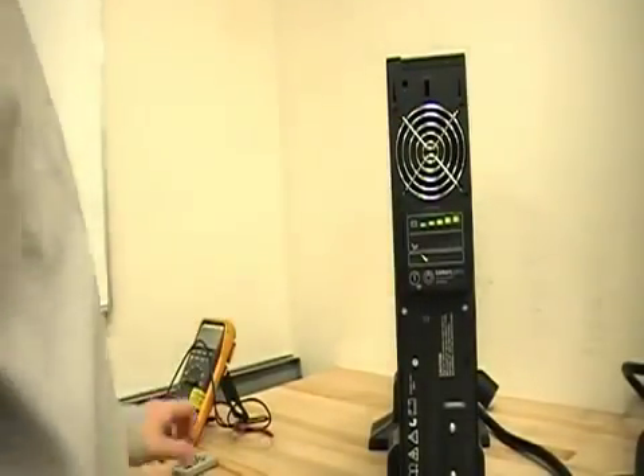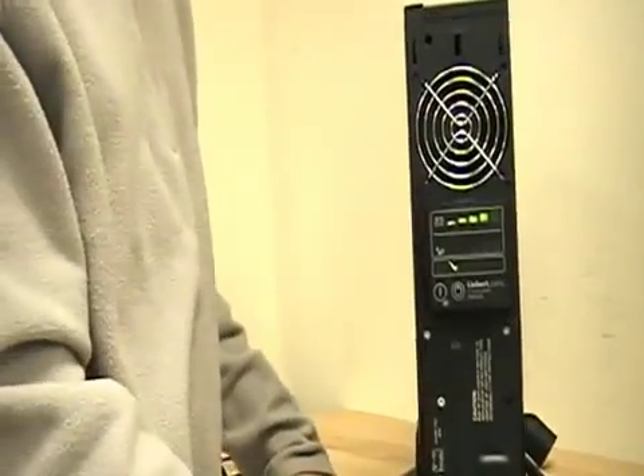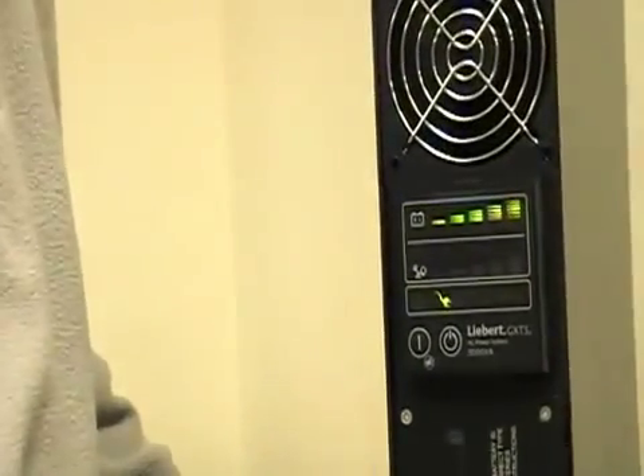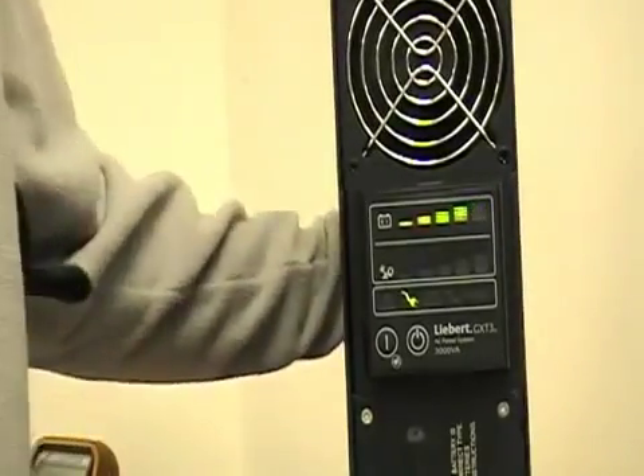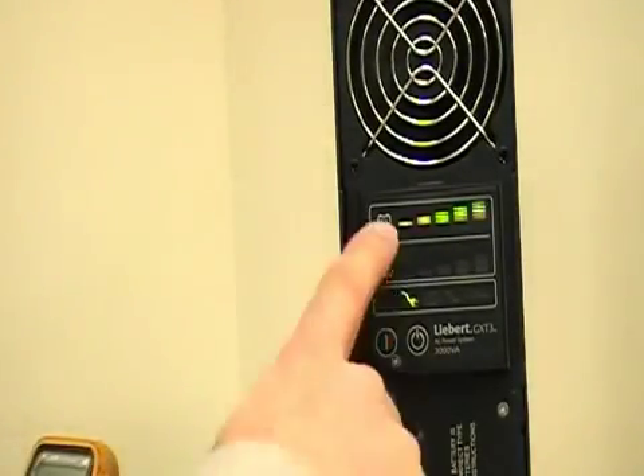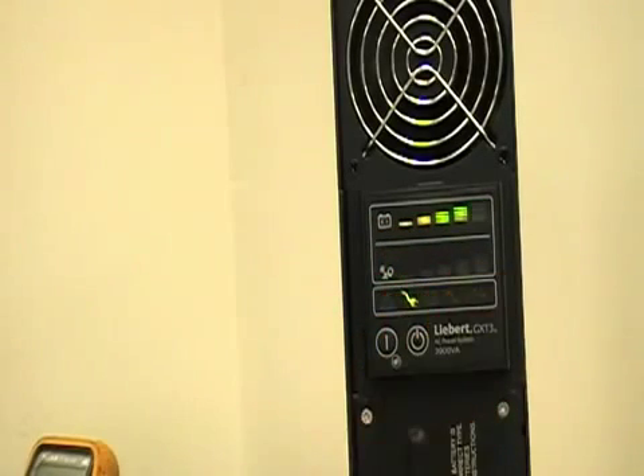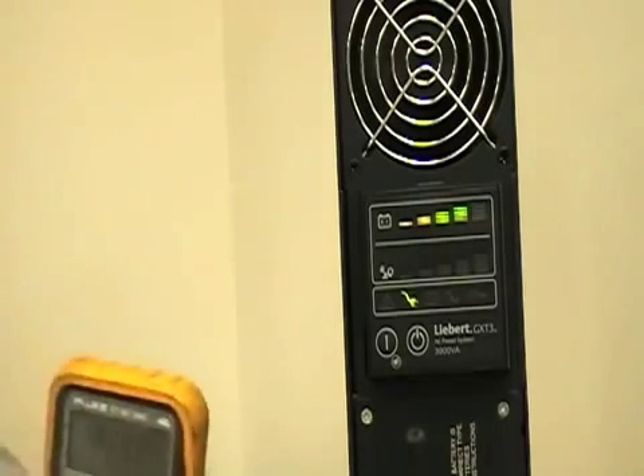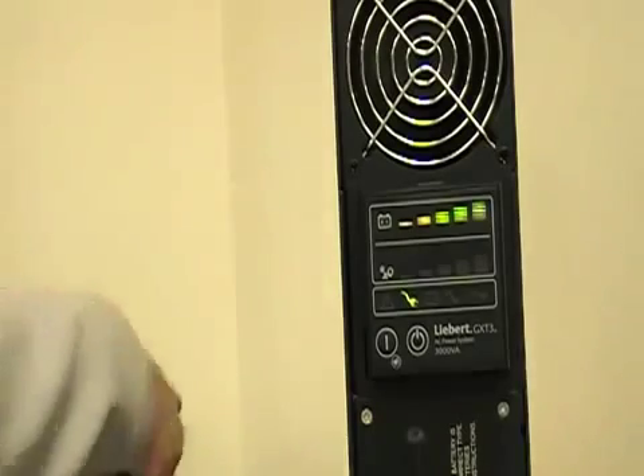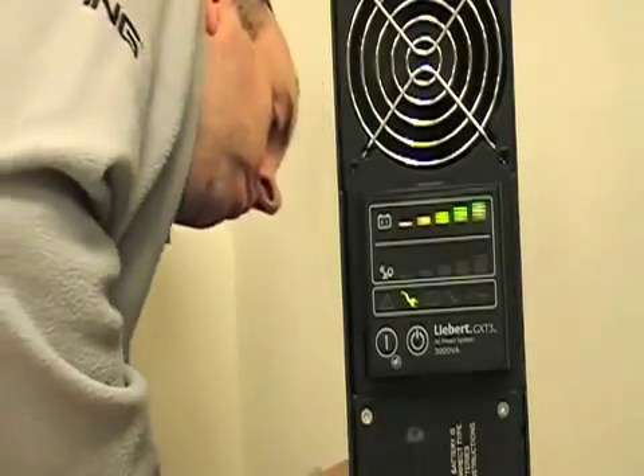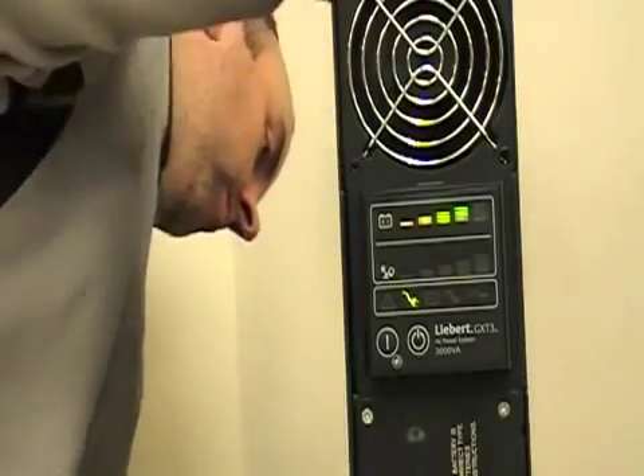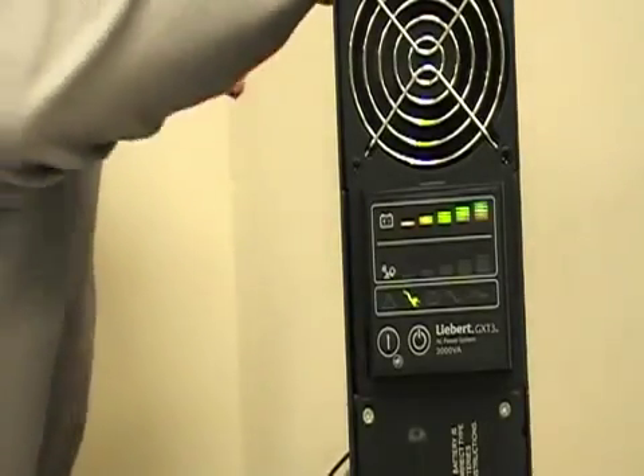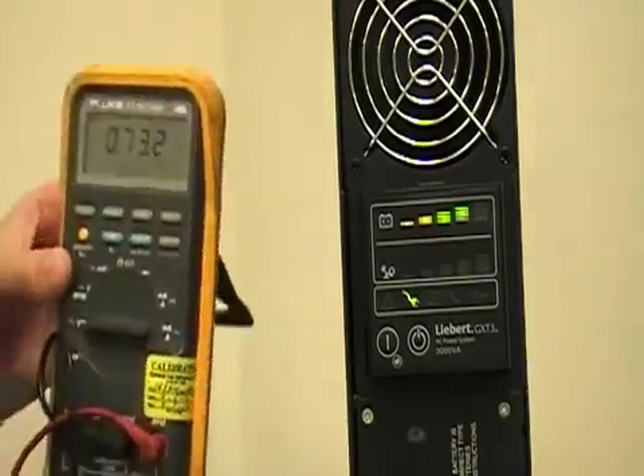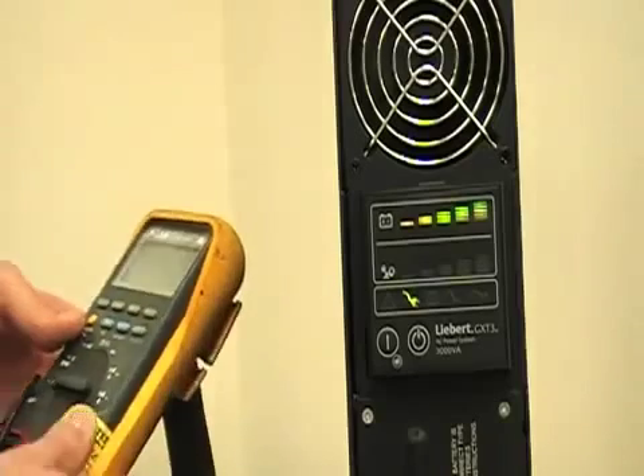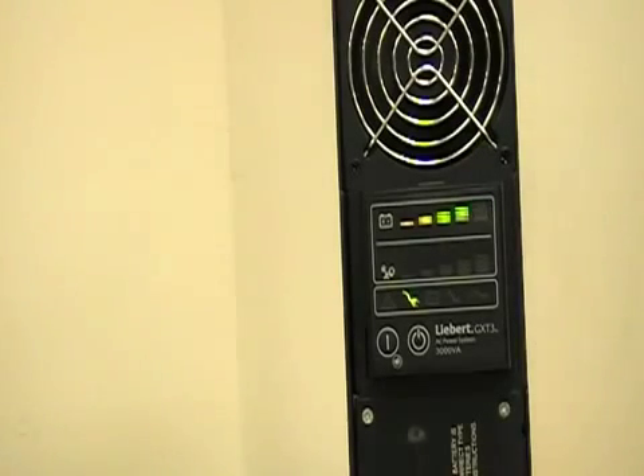Unit powers up, we get a couple LED indications. Okay, get that centered for you guys. Alright, a couple of indications here. We have a battery charge indication and we have a load indication. Right now we have nothing on the unit. What I'll do is I'll put this meter on the output of one of the 15 amp plugs. Okay, so right now we got 73 millivolts across there. Essentially it is off. Getting a little bit across there.